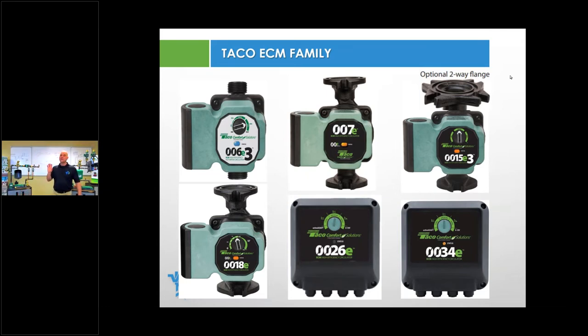0015E3. This is probably one of the best service pumps you could have on your van. And if you get it in the four-way flange configuration, this will cover basically from a 003 range all the way up above a 008 range on your typical home. This gives you the flexibility to put it on low, medium, or high and hit that whole range of circulators.